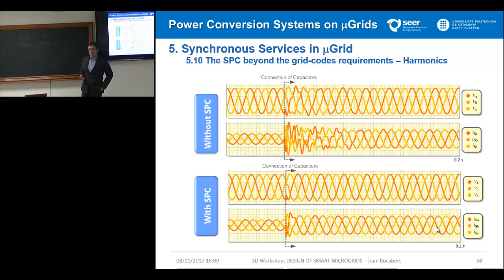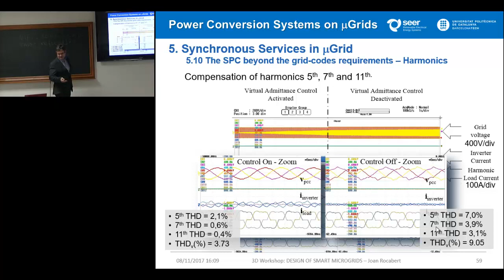This is a perturbed voltage due to a large harmonic load, without the support of the inverter. We activate the SPC with different admittance at different harmonic conditions. This is the voltage that we are going to get, supplying the same load. We are able to detect the harmonic voltage and restore the system again to its operating conditions.